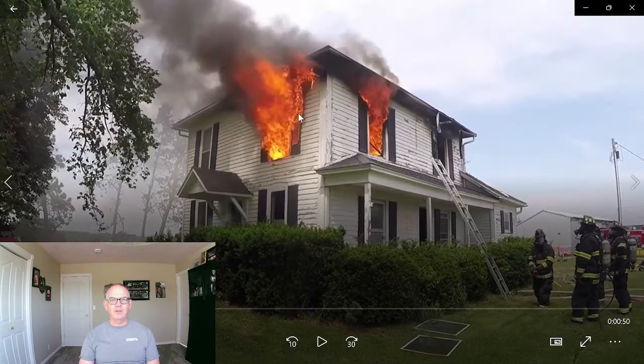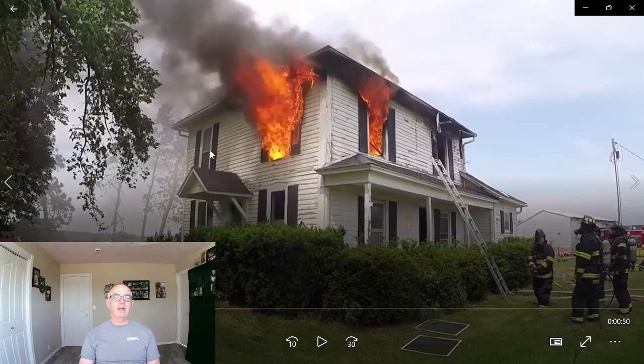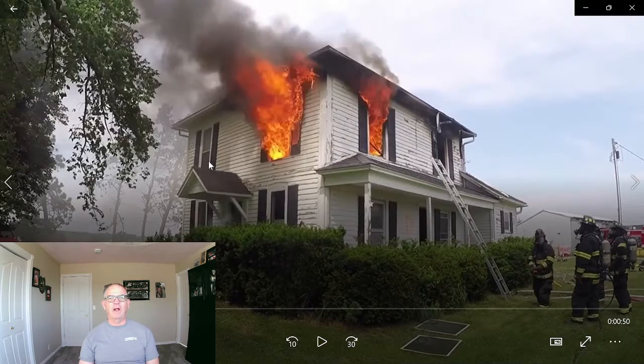One is, if the door to this room is closed, then you would not see smoke coming out of these other spaces. If the door to this room was open, but the doors to these other spaces are closed, you're also not going to get enough smoke to have it be coming out of the cracks around the window. But bi-directional flow way up high here — still enough pressure to come out against the wind. We'll go right through when they make their fire attack.